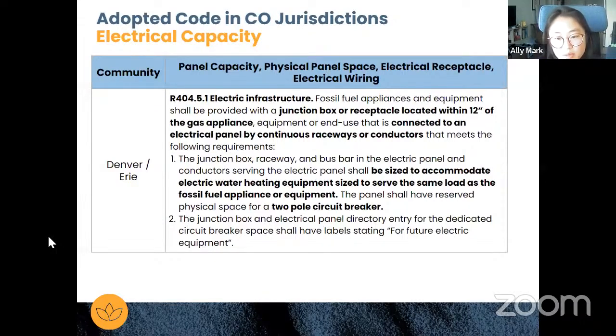The junction box, raceway, and bus bar in the electric panel and conductors serving the electrical panel shall be sized to accommodate electric water heating equipment, which is sized to serve the same load as the fossil fuel appliance or equipment. The panel shall have reserved physical space for a 2-pole circuit breaker. And the junction box and electrical panel directory entry for the dedicated circuit breaker space shall have labels stating for future electric equipment. So that's kind of striking that middle ground of having some requirements be very specific and leaving it a little bit more vague depending on the load that the fossil fuel appliances are imposing.